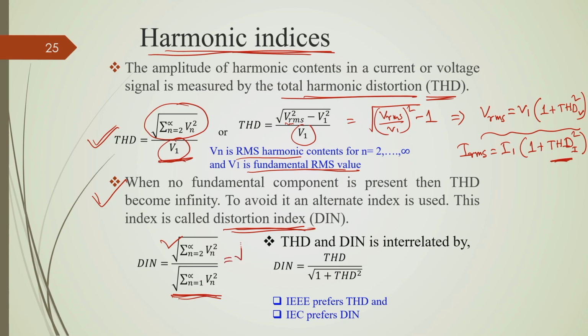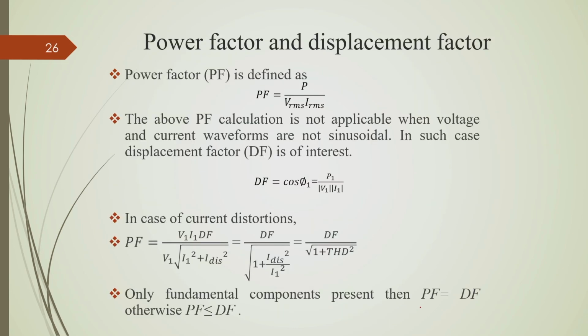So, this one is similar to V RMS. The numerator is the same as that of THD, that is, the summation of n equal to 2 to infinity of V n square, divided by V RMS. So, the relationship of DIN and THD you can also find out. IEEE prefers quantifying harmonics by the THD index, whereas IEC prefers the DIN index.